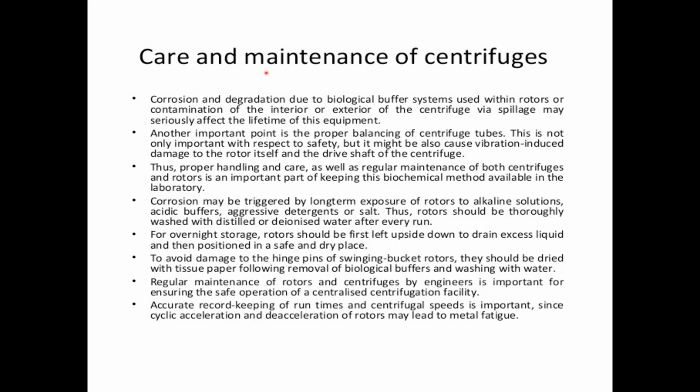So what is a problem with centrifuges and with the mobile parts of the centrifuges, which are the rotors? Well, they are all made of heavy metal pieces and parts, and therefore corrosion and degradation due to the quite aggressive biological buffer systems you are using will damage rotors and can contaminate the interior or exterior of the centrifuge due to spillage, and this may affect the lifetime of the equipment.